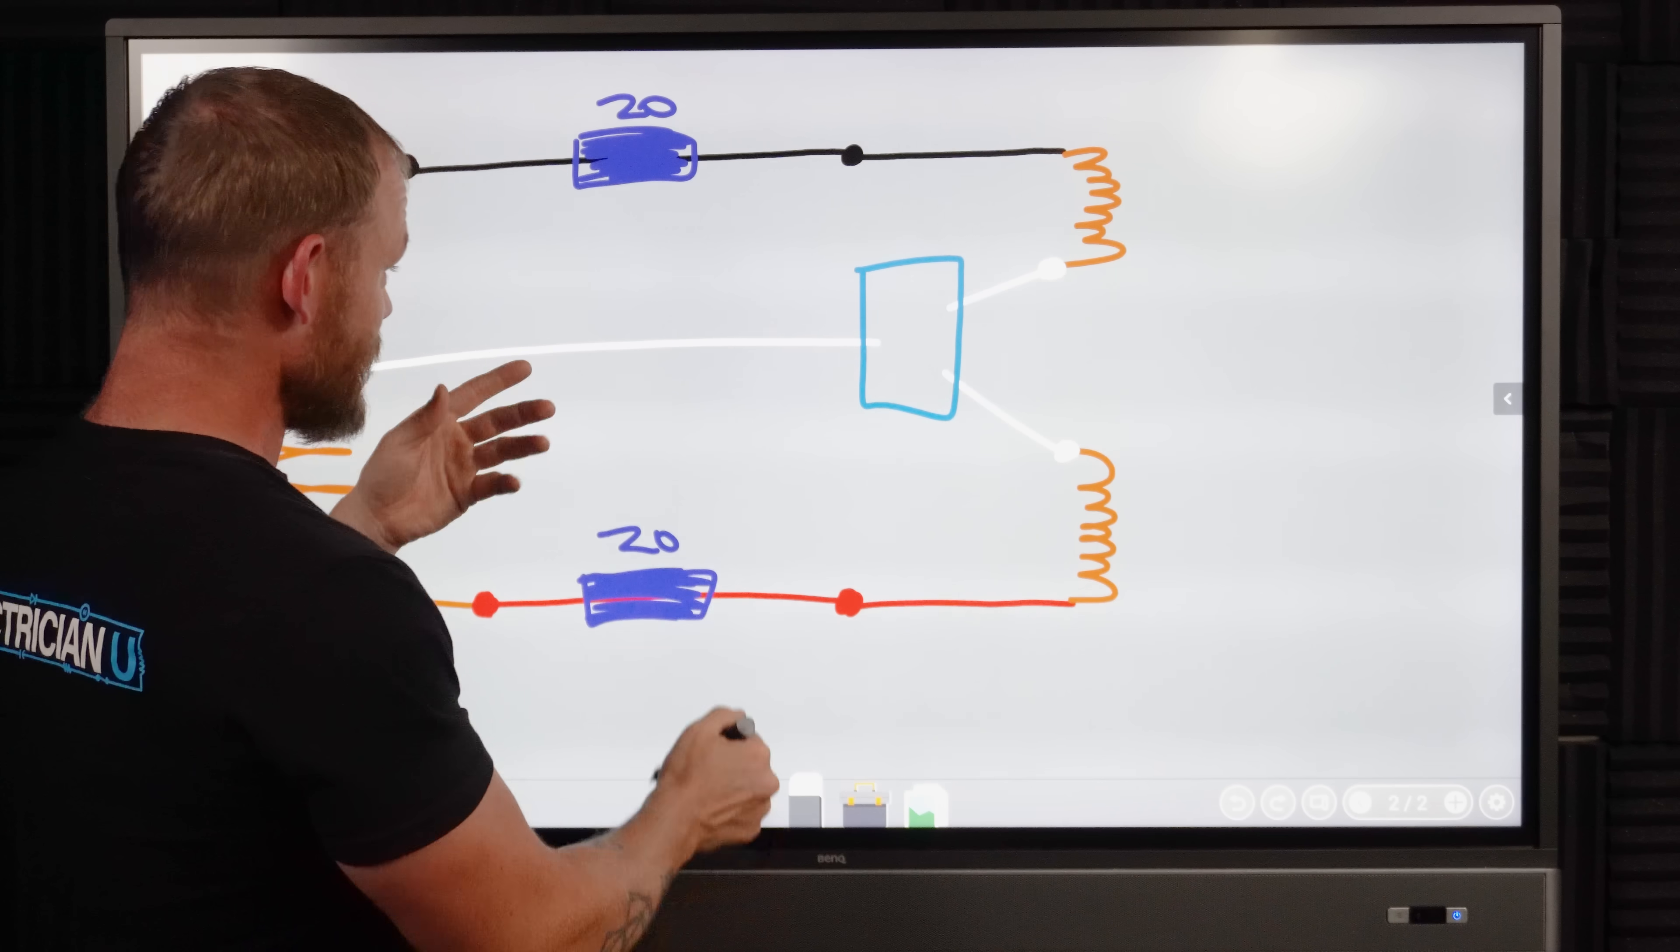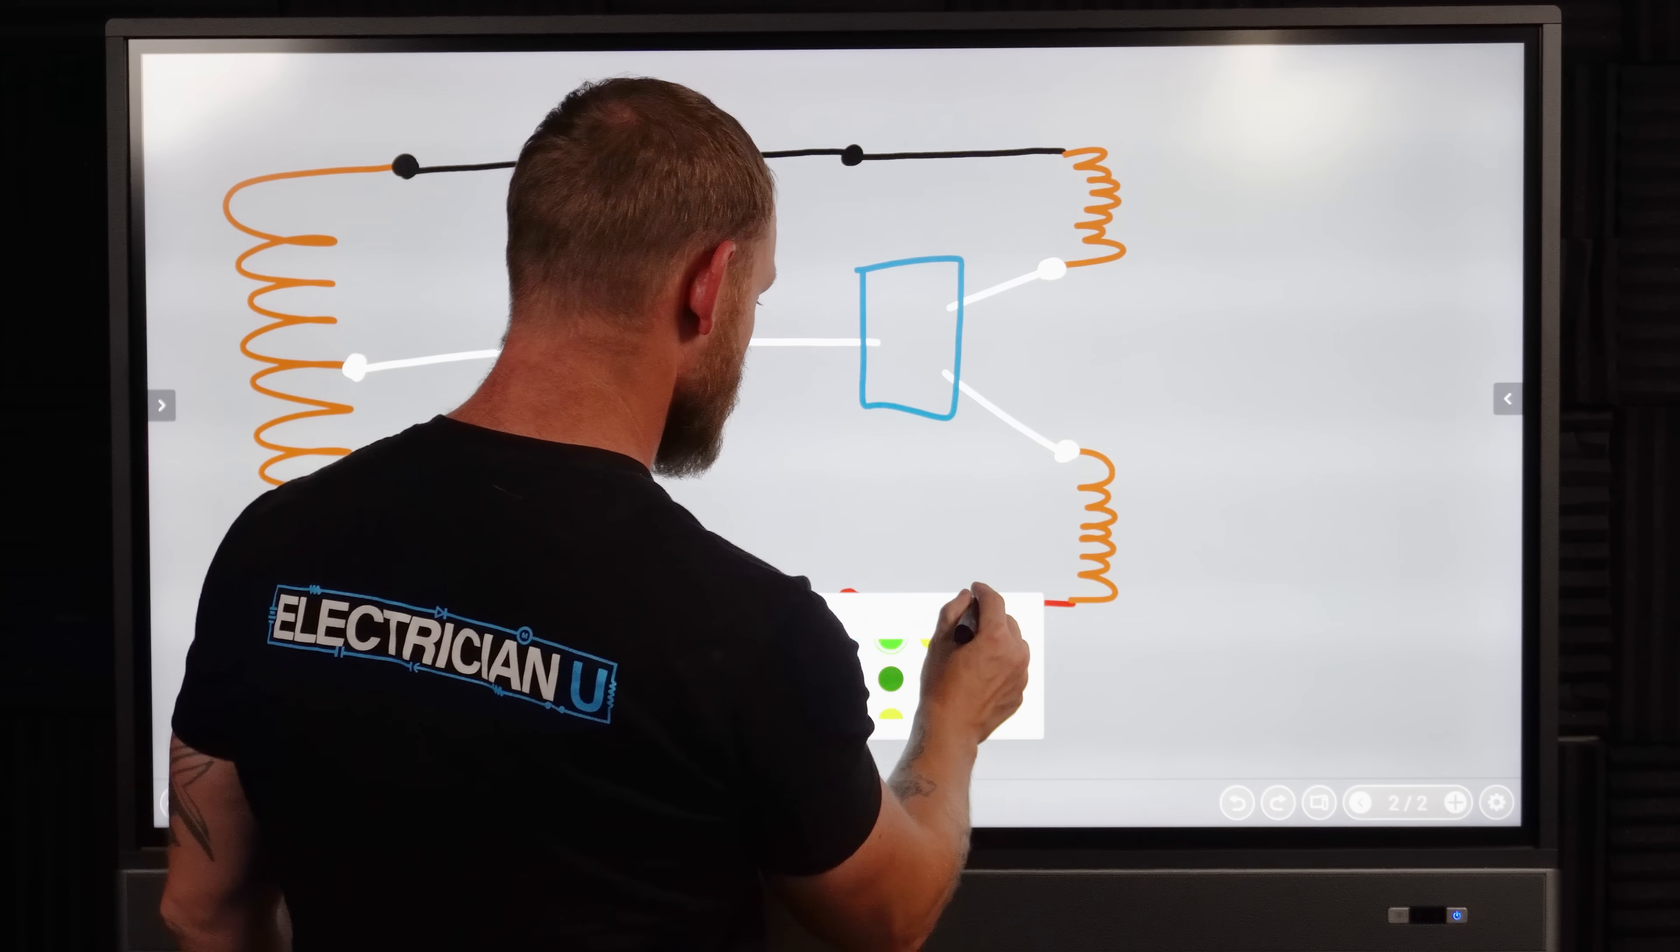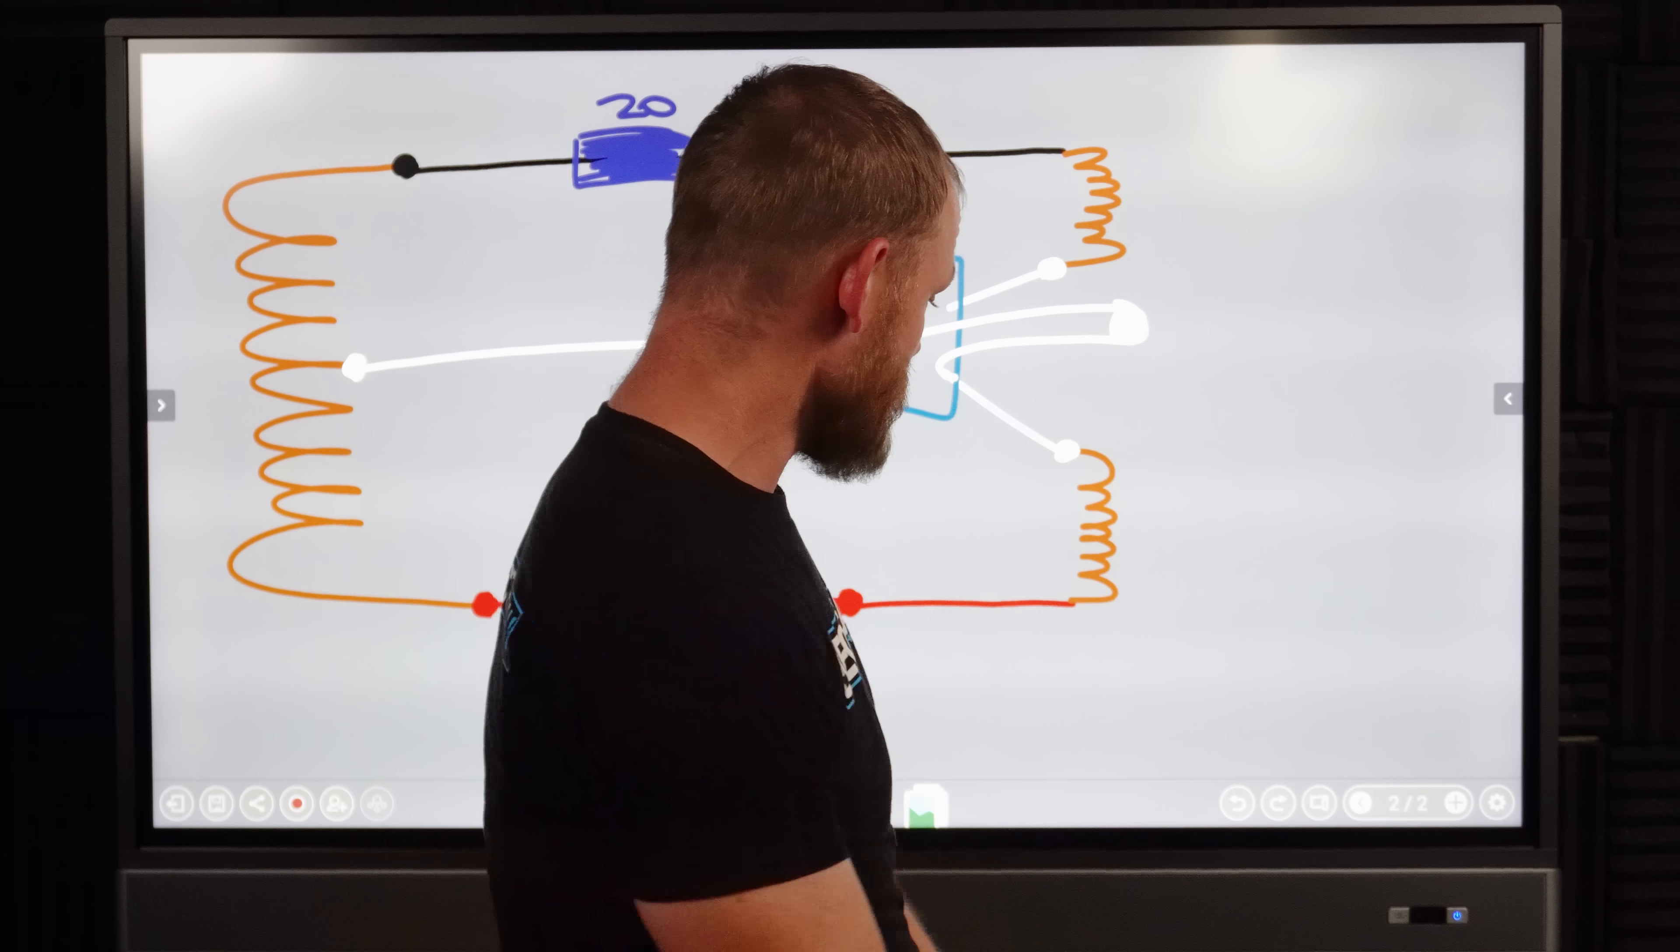We just decided to reach our hands in there, open up neutrals first, and just disconnect all neutrals. Well, we just basically nixed out this wire, right? So like now this whole wire is not a thing anymore. It's still got potential between here and here, and it's still got potential here and here. So you could get shocked between these two neutrals. If you have like both of these neutrals sitting out, hanging at the box, and you're just being Mr. Awesome over here, and you touch between those two neutrals, you're going to get shocked. You're going to get 120 volts going right through you because now you are completing the circuit. There's a complete path through that whole thing. So you got to be careful about that.